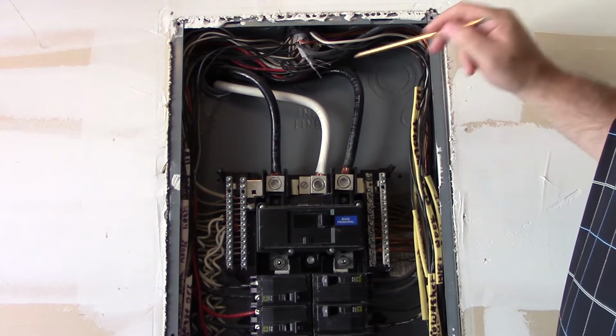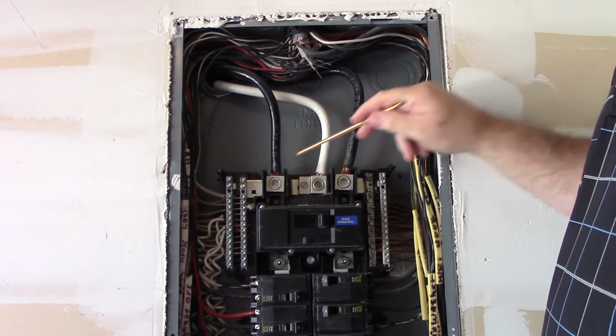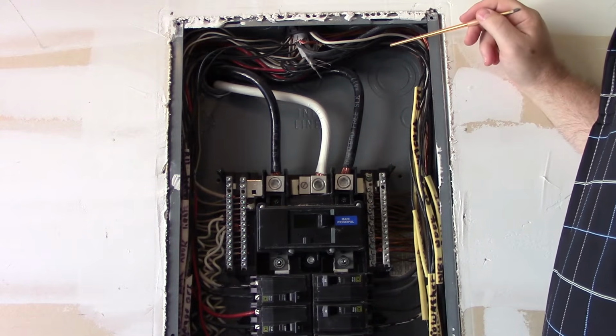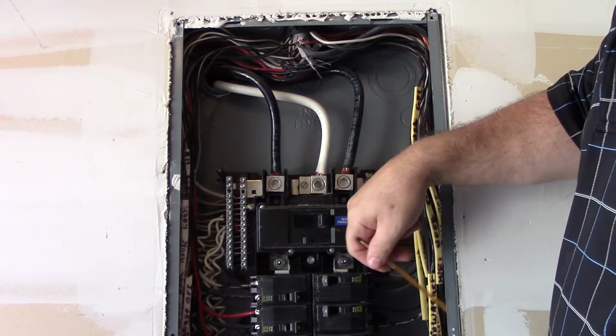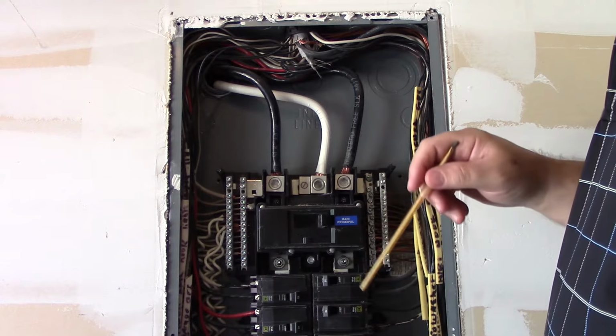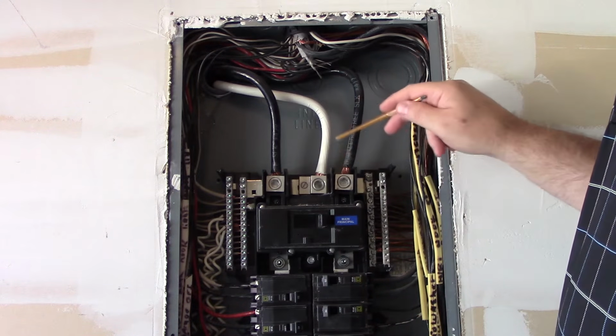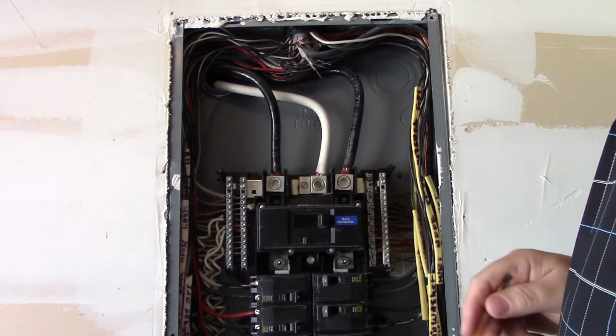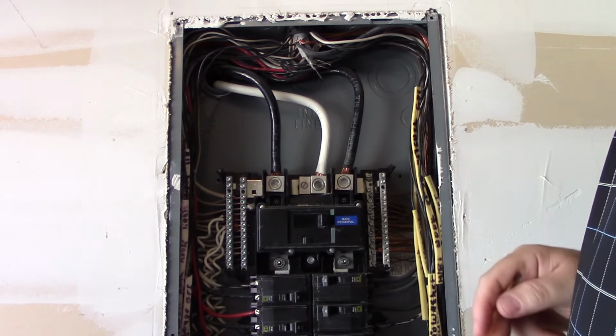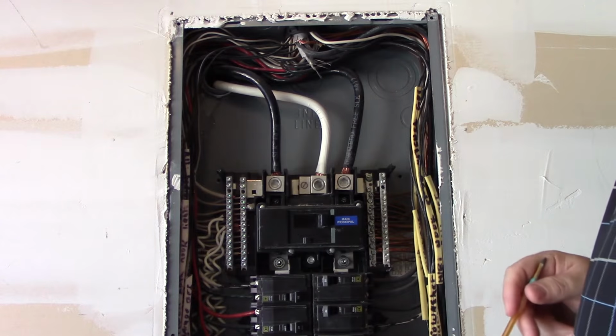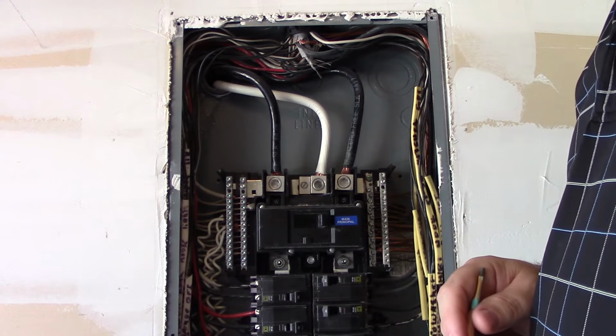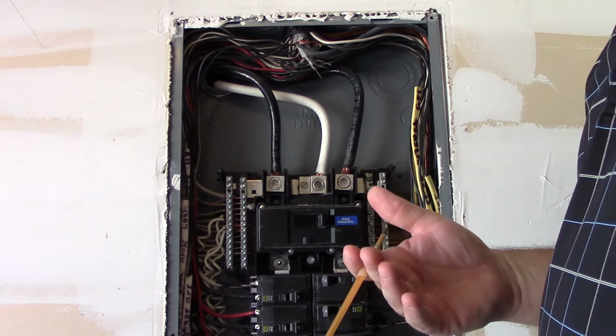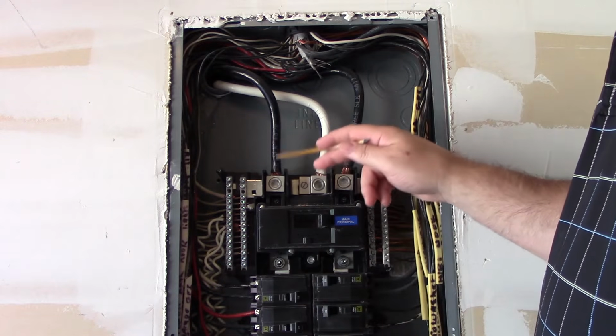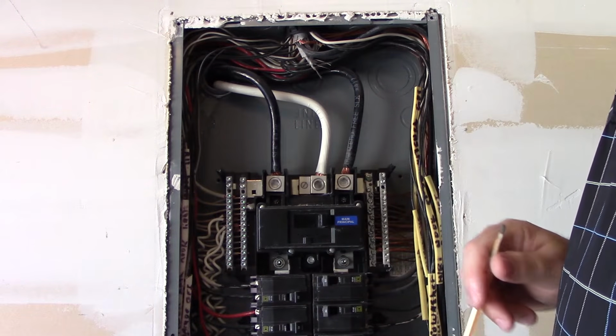But now we need to size these conductors and make sure they're the right size. Now these terminals are based on 75 degrees C, as the legend over here is going to tell us, and we'll see that in a little bit. So we know that these conductors right here have to be at least 75 degree rated insulation, and that's pretty typical for the building industry today. In fact, they're probably all going to be rated 90 degrees C, but that's for adjustment and corrections. We are going to be limited to the terminals. So these terminals are at 75 degrees C.